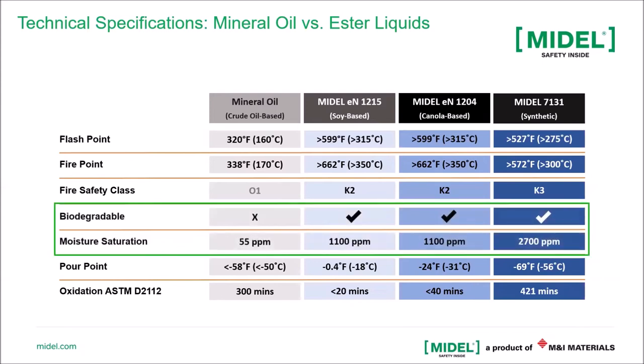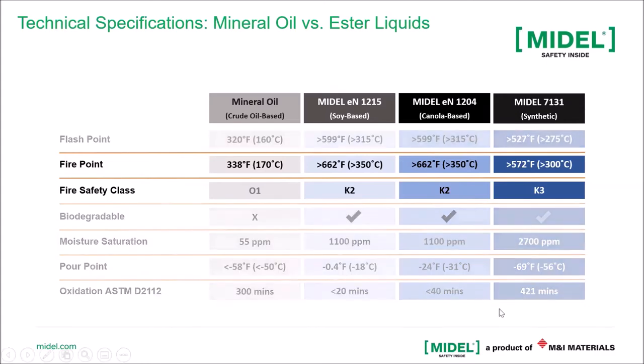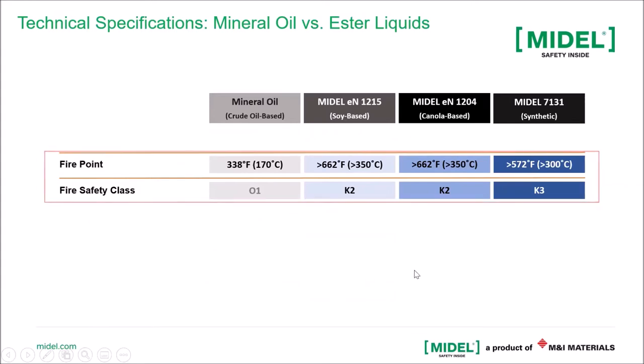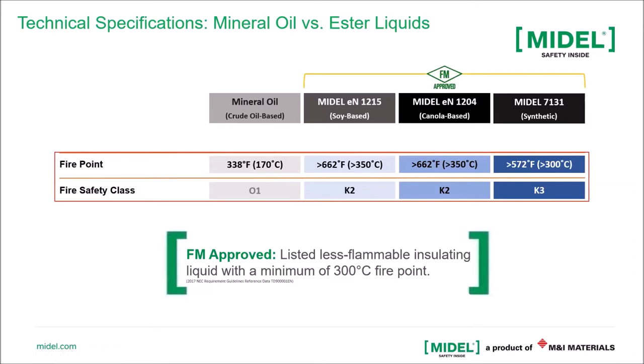We'll focus in on moisture saturation. I just mentioned why they can take higher moisture saturation and not have a voltage breakdown. You see, moisture is a big problem for mineral oil, and everybody who uses it is worried about those 55 parts per million and exceeding that. You see, you can go clearly up from there, and especially with MIDEL 7131, without any issues to the electric performance of the liquid. And then you'll see that all of the esters, the MIDEL esters, are biodegradable and mineral oil is not. Now, the biggest point for design engineers and substation designers is the fire point and the fire safety class. To be K class or FM approved as a less flammable insulating liquid, you've got to be over 300 degrees C fire point, which you see all three of the MIDEL esters are.